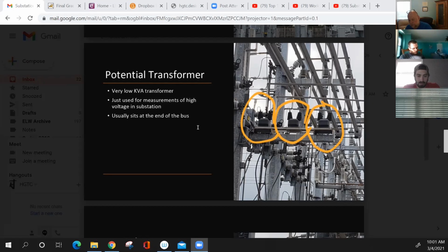So it's more or less like you're reading 120 volts or 240 volts phase to phase, just like on a secondary voltage. That's how they transform that down, so that 120 volts was in relation to 13,200 and 240 volts was in relation to the 23 kV. So it's a very good piece of equipment. And the engineers would be able to monitor to make sure everything is okay as well. The way technology is today, they don't have to actually go into substations anymore unless there's a communication problem. They can monitor each breaker from their desk to see what they're doing, how many amps each phase is pulling, those kinds of things. So it's a good piece of equipment in the substation.